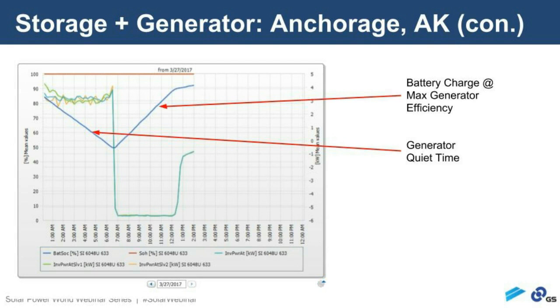The inverters drop off, and then the generator comes online, and you'll see the blue line coming up to the right where the batteries reach full charge again. And from a generator standpoint, this works really well because the generator can come to peak efficiency. So it'll ramp right up to maybe 80% of its load rating, handling the site loads, charging the battery as fast as it can, or at whatever the predetermined rate is, until the batteries reach their float voltage. And then you can see, again, the inverters start coming back online, preparing for the next day.